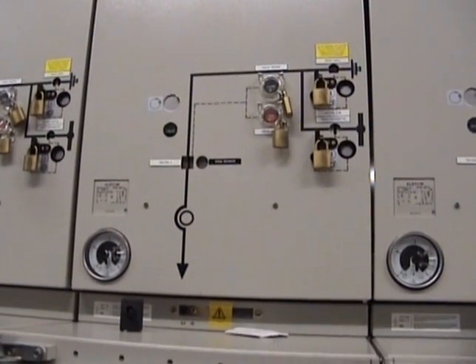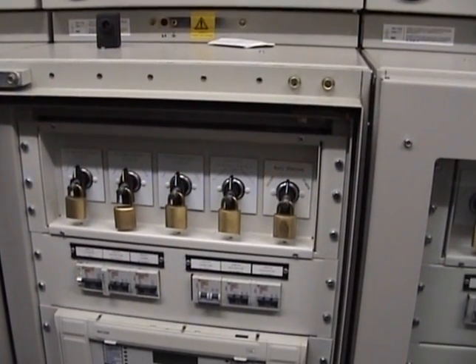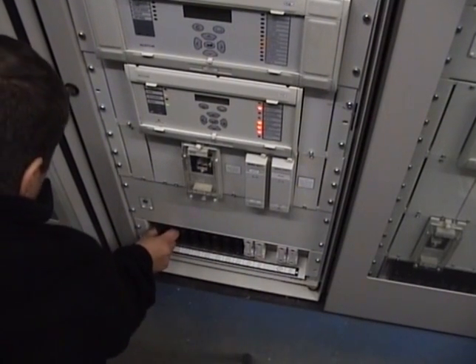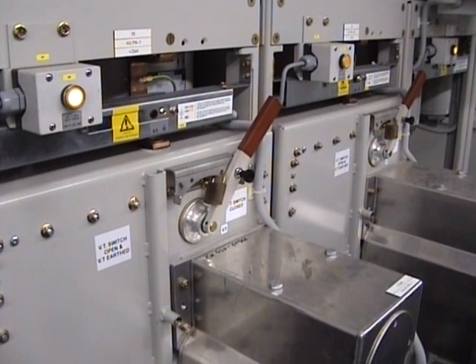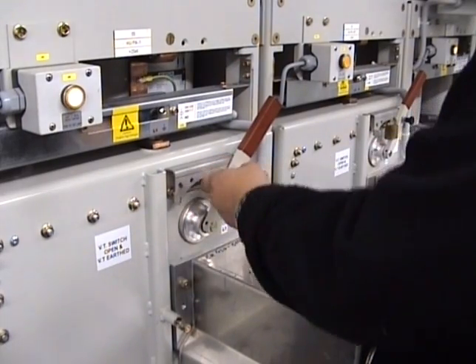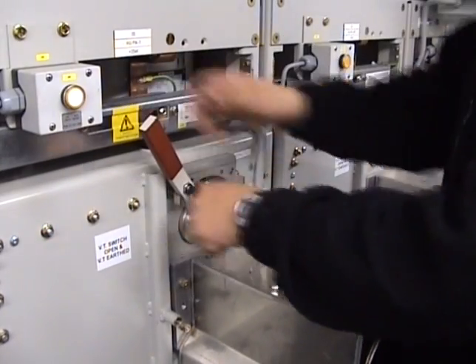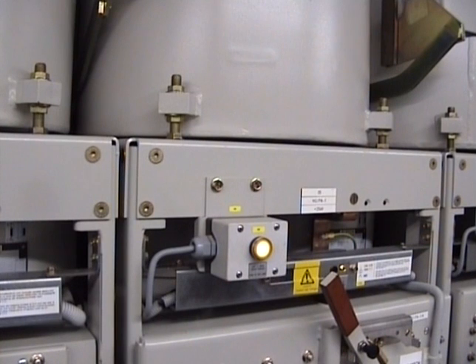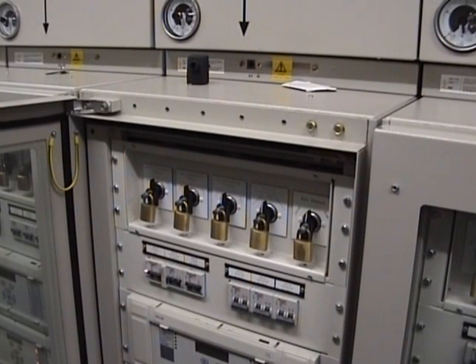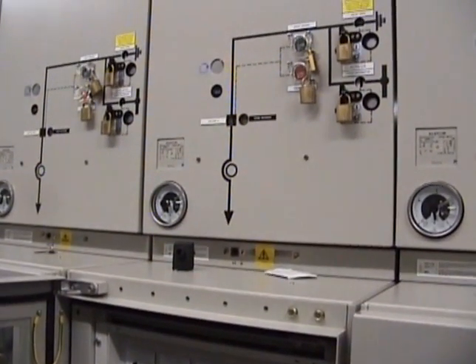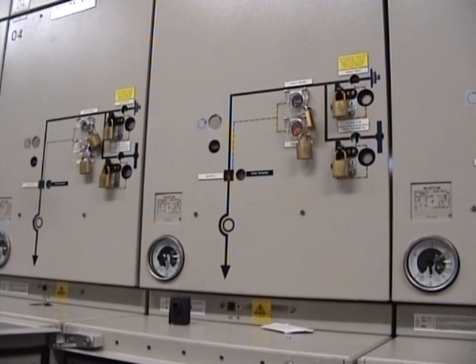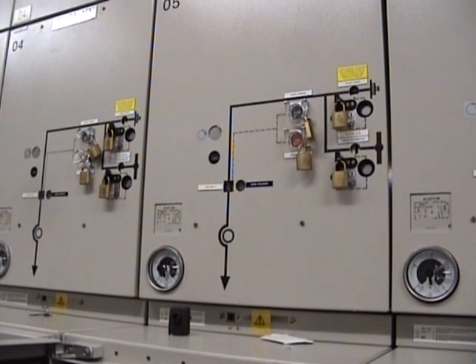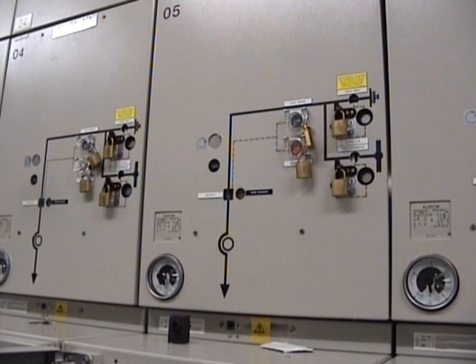Now that we have the cable earthed, we next switch off the disconnector and earth switch MCBs, and we remove the trip and closing fuses from the lower part of the panel. At the rear of the switchgear, we now place the VT isolator into the open and earthed position. We also see the indicator showing that the outgoing cable is now connected to earth. We now see that we have applied padlocks to the control switches and to the push buttons that operate all the equipment used for this isolation. The keys to these padlocks will be placed in the lock-off box, and a unique lock-off box key will be given to the recipient of the permit to work along with the permit to work.